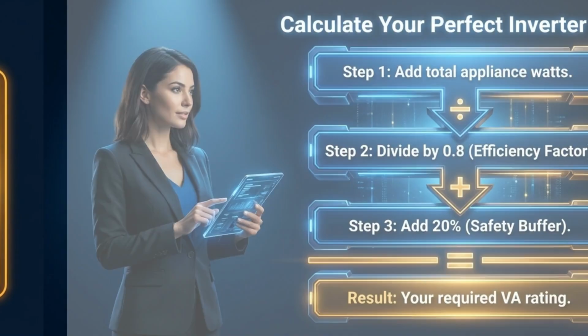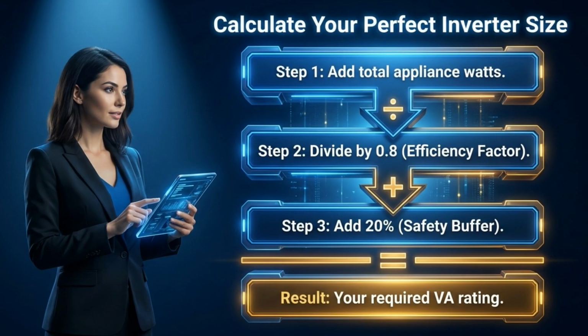To calculate your perfect inverter size, follow these steps: add your total appliance watts, divide by an efficiency factor of 0.8, and add a 20% safety buffer. The result gives you the required VA rating.